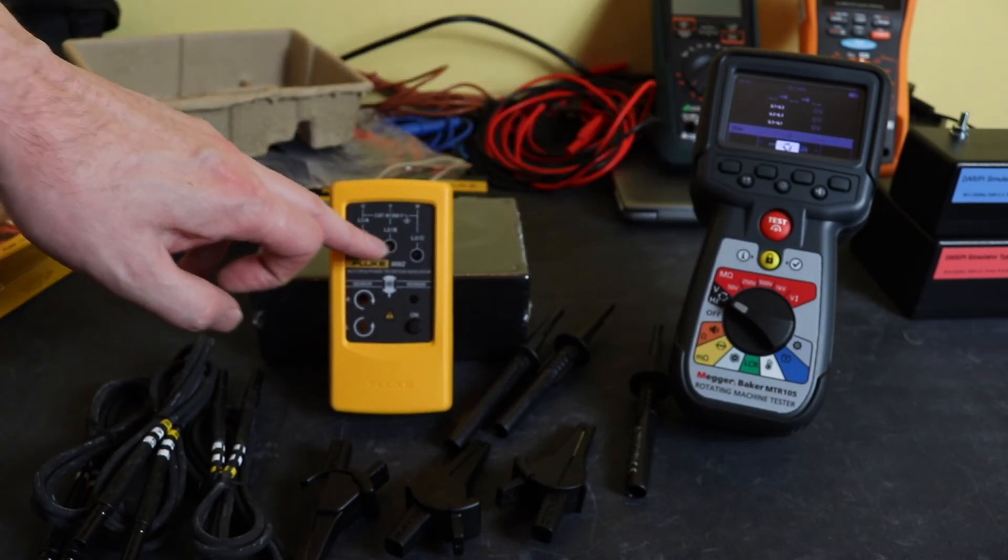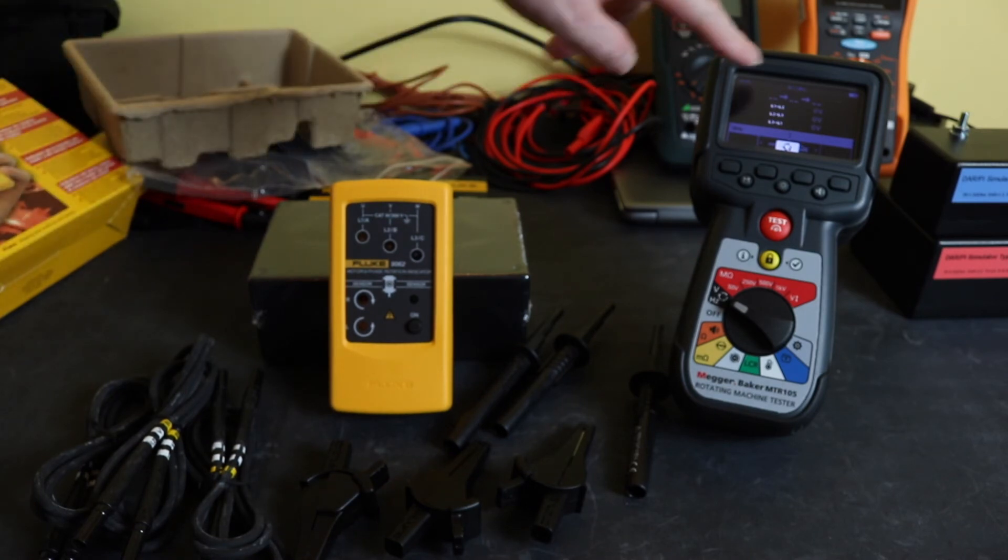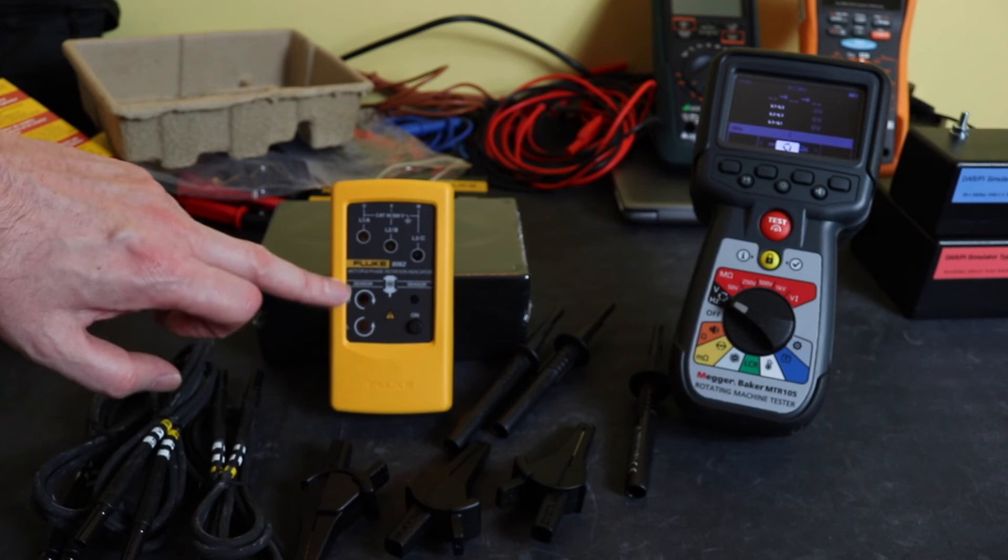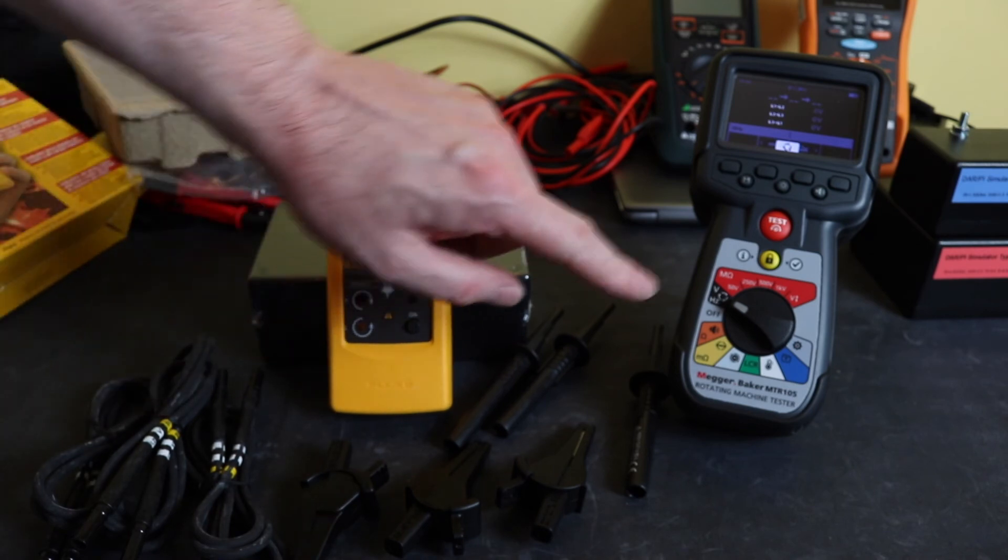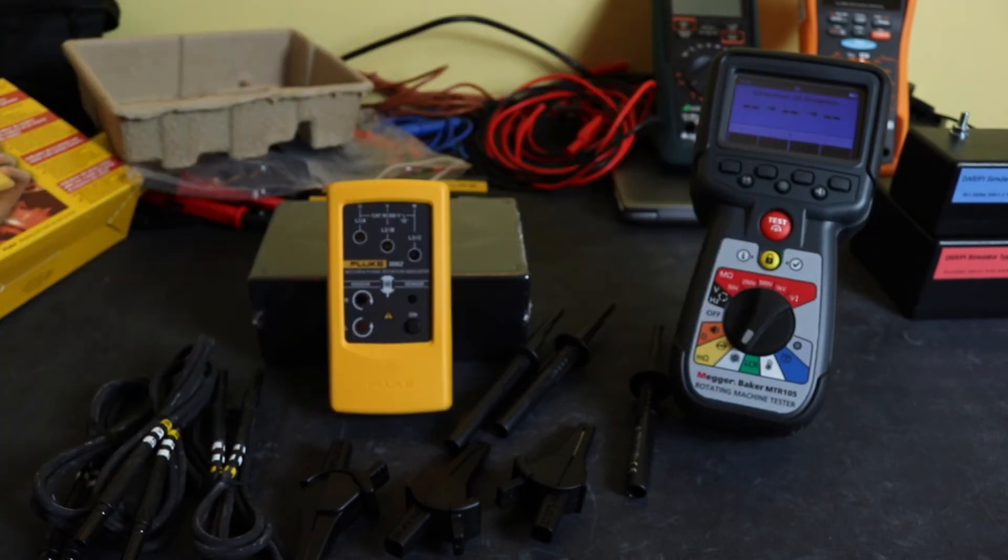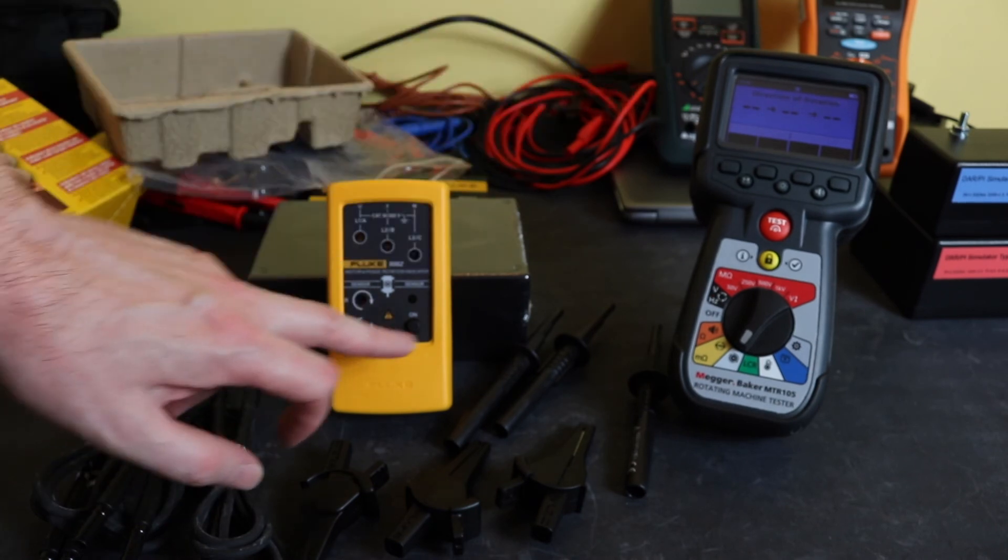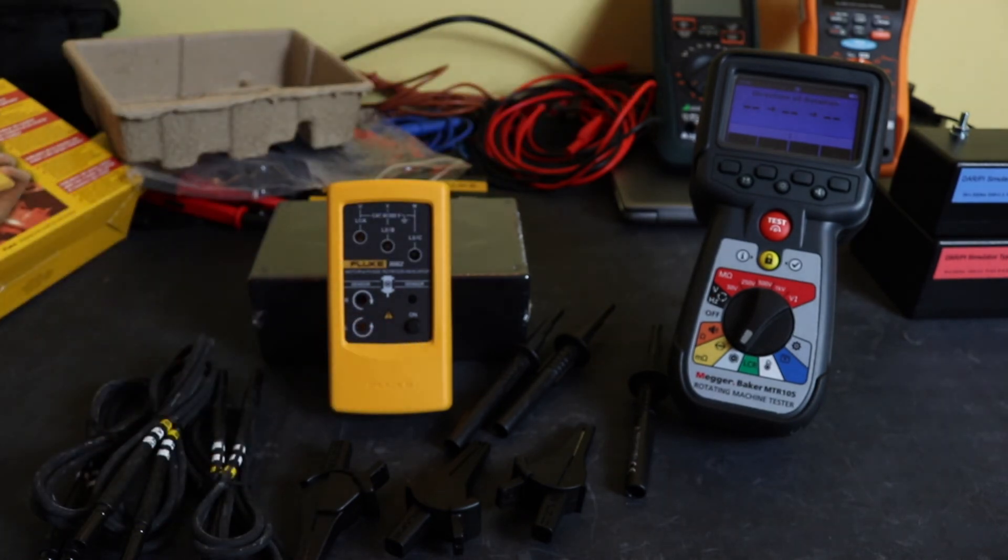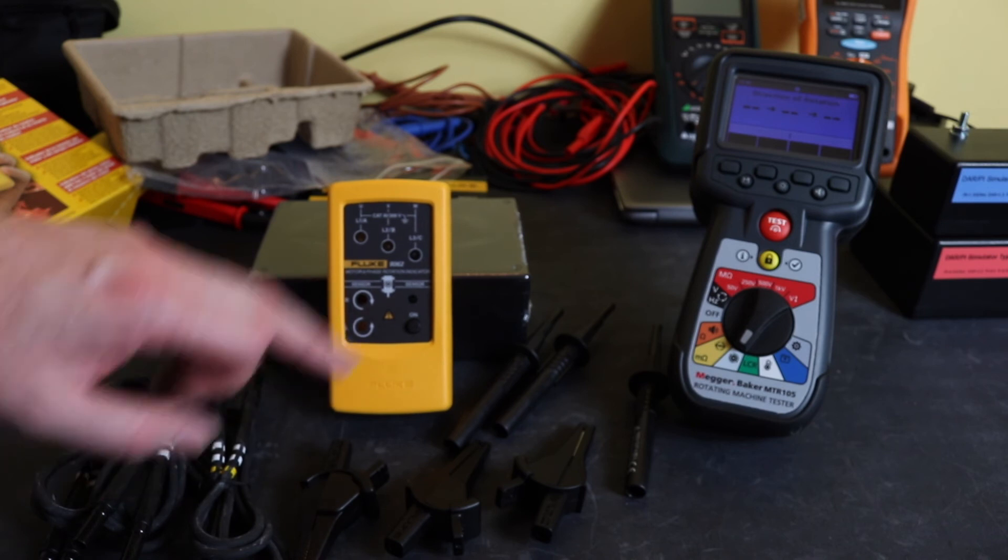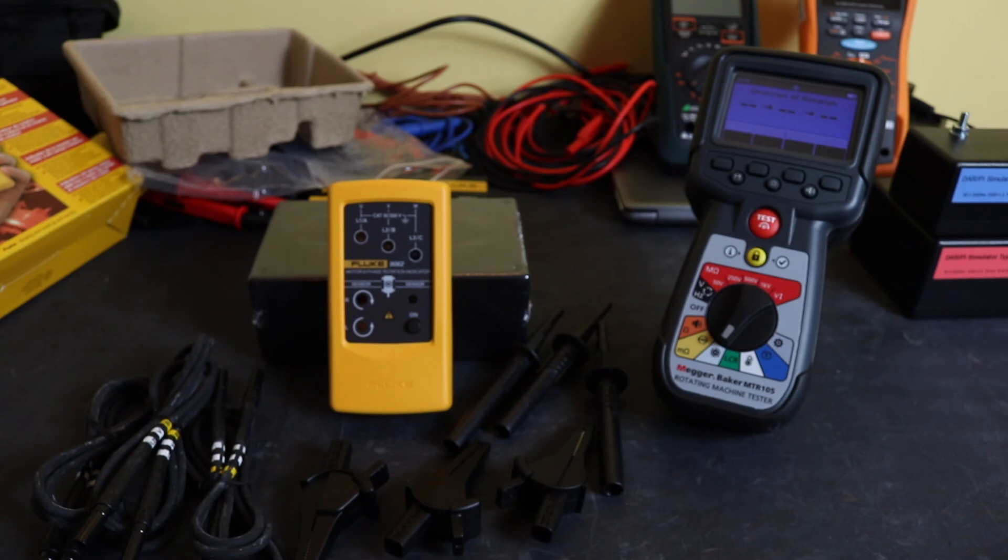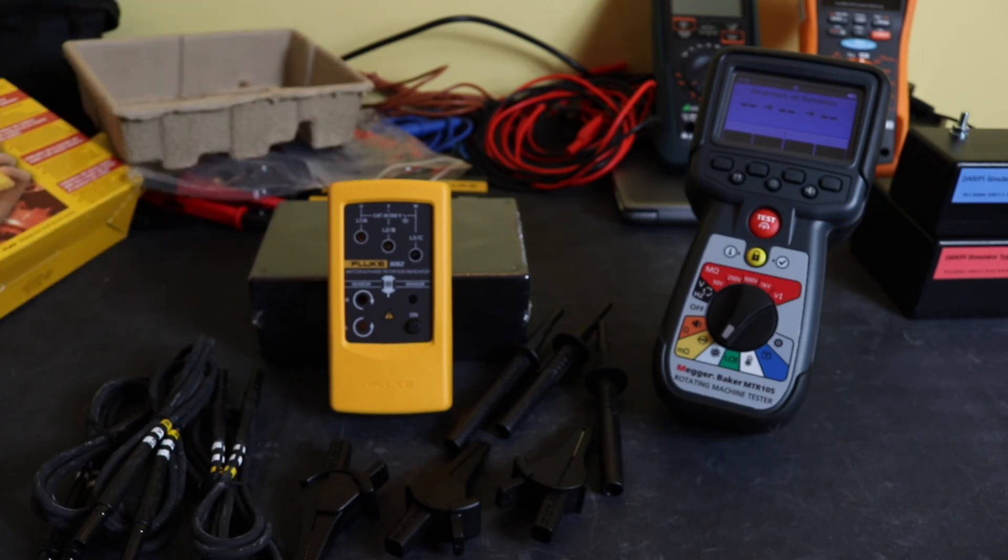I've got a three-phase voltage mode, which will be these three lights up here, and it gives phase rotation with these two lights down here when it's powered up. Then swing around to here, we have a motor function which you need to energize the meter with, and again you'll use these two lights. Whereas with the MTR105, it's just the arrows there to show the direction.